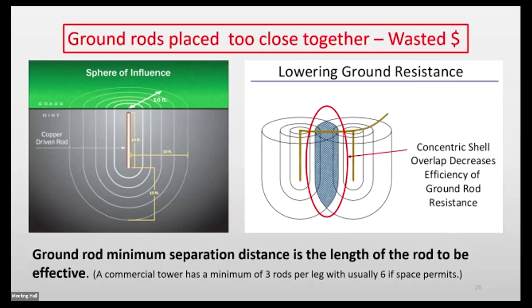We talked about distance apart. On the far right side there are two semicircle drawings, and you can see a gray area of concentric overlap in the middle. When the rods are too close together, that grayish color is the area of lost potential grounding, because the rods are too close together. Just understand that exists. It's great to put them in, but it's useless if they're closer than the height.